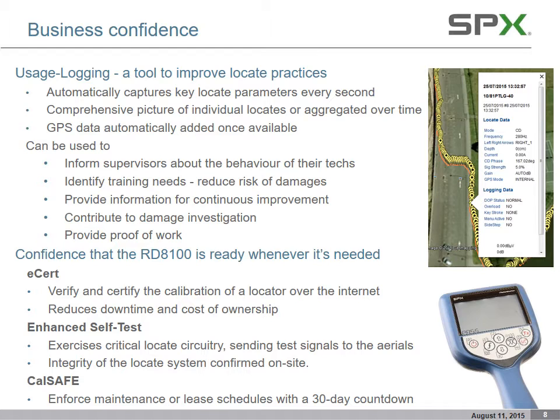Now, the GPS portion of it - the nice cool thing about the GPS is not only mapping, but the logging portion. The logging portion allows you to understand where you've located, and maybe if you need evidence to show that you've located the line because the contractor took marks away, or they're just not there because it snowed or rained, you have a way to download that information. That information is stored over 500 days worth, and that's if you've worked 8 hours a day, so it might even last longer. You can download that info, and it's not just the location info - it's the frequency used, the depth readings, the current measurement reading, and the date timestamp, and so on.